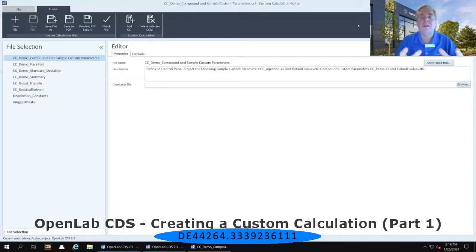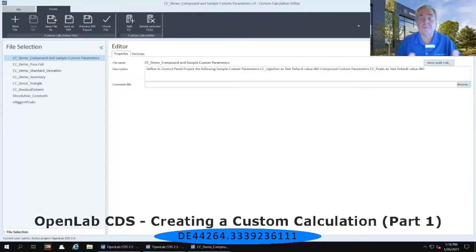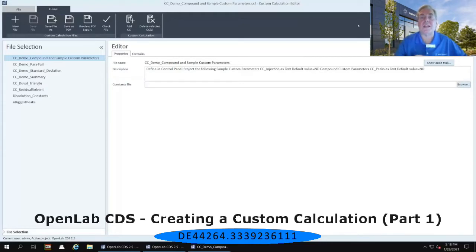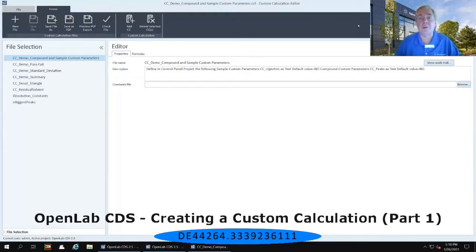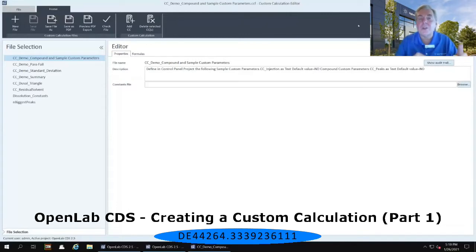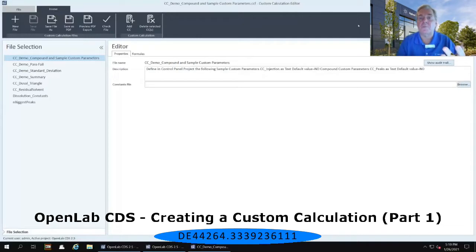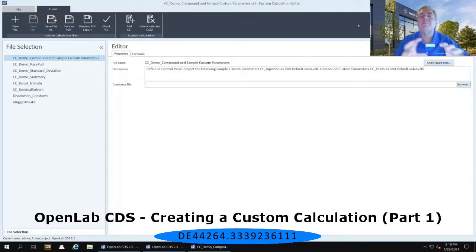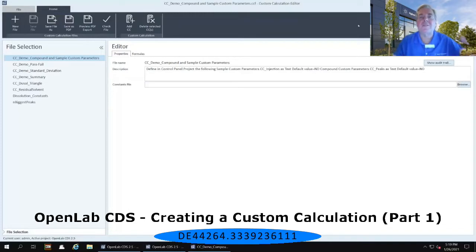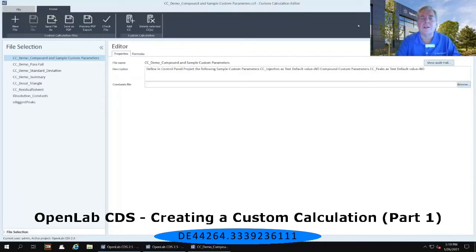So not only do I want it to calculate what that USP resolution is, I don't want to have to remember what the specification was set by my QA QC folks and my SOP. So I am going to create a custom calculation file that will tell me that if the USP resolution is greater than 13, then it's going to mark a pass in the column of my result table. If it is less than 13, it is going to mark a fail in that column. So it gives me an opportunity to add some logic so that I can start using the computer as the tool it was meant to be rather than having me be a slave to my memory.